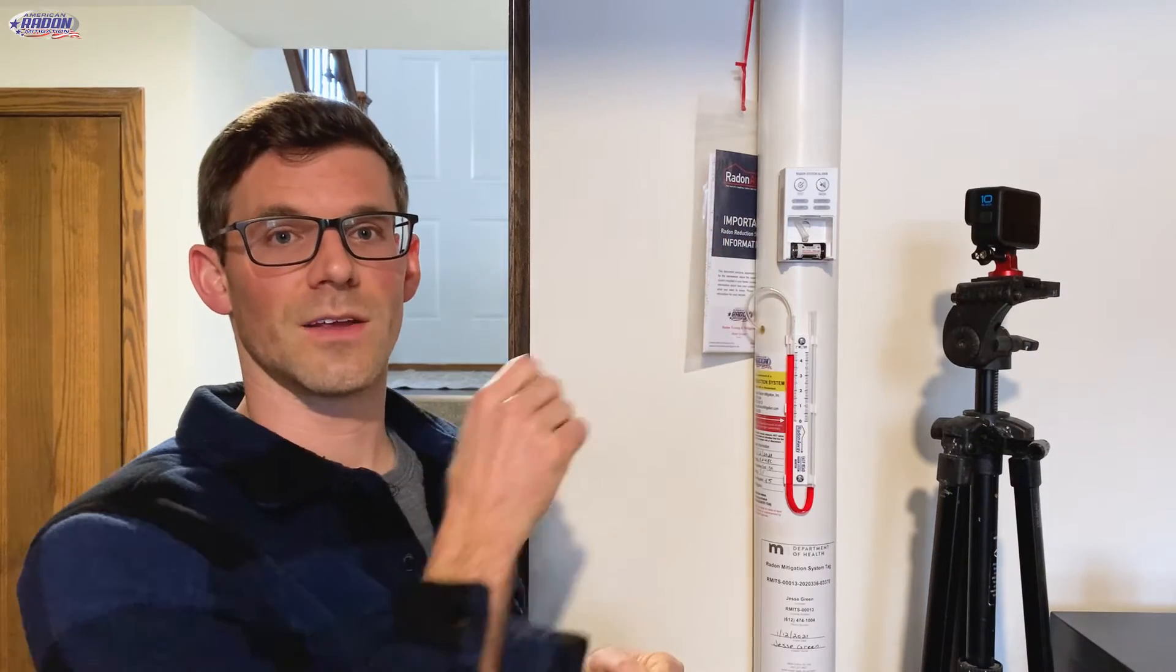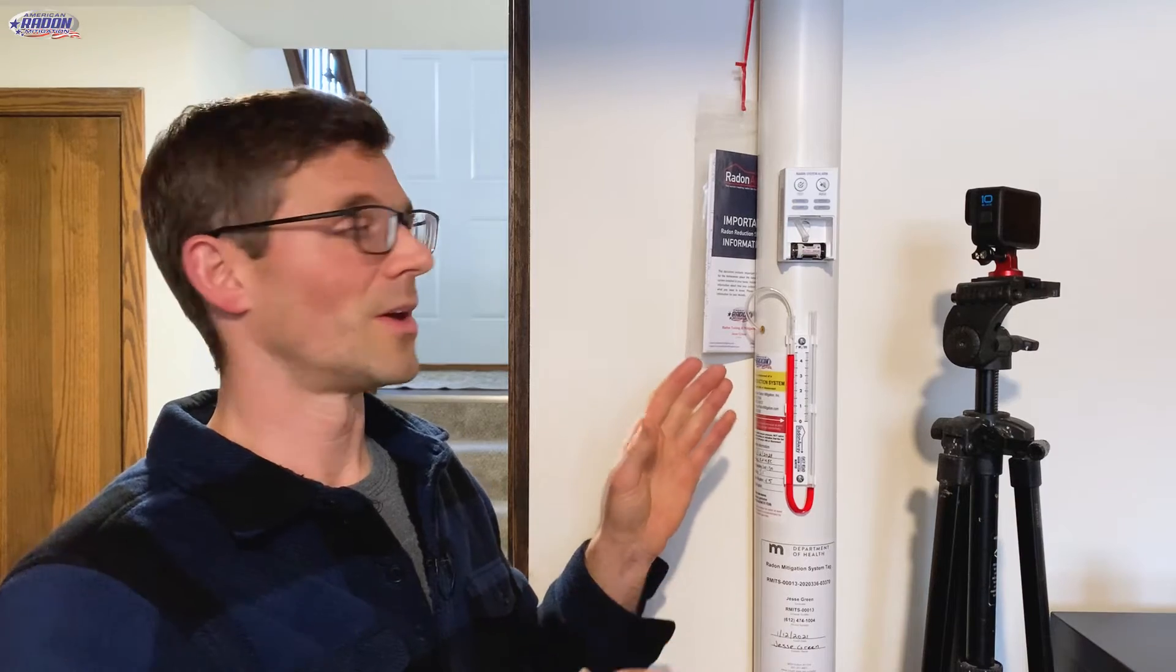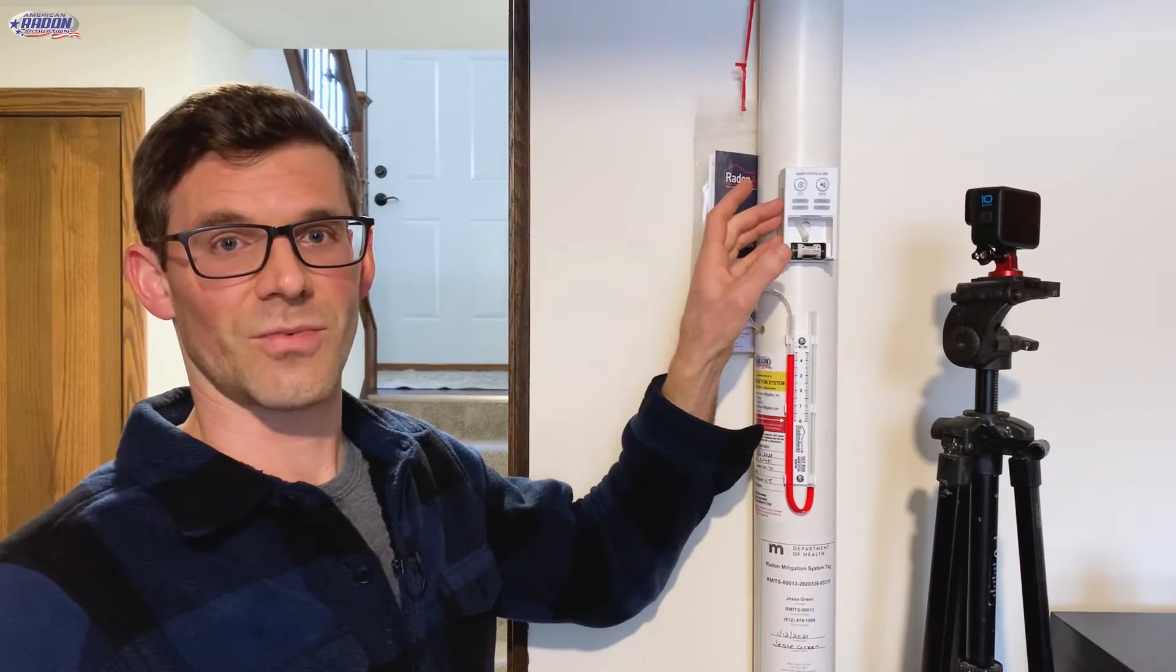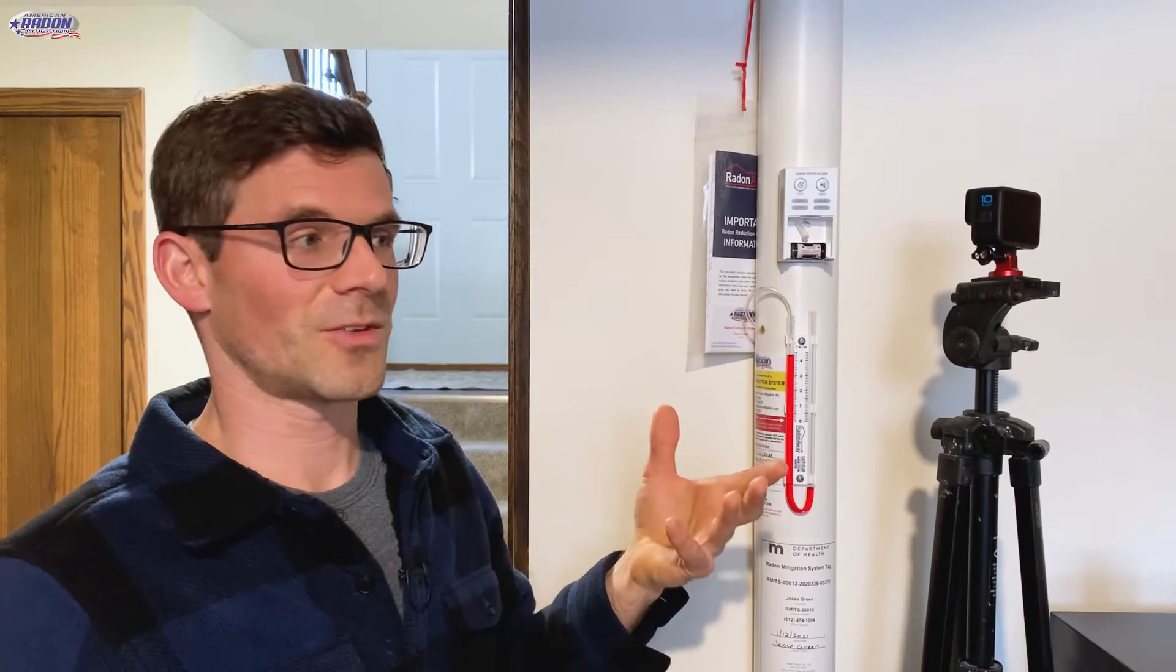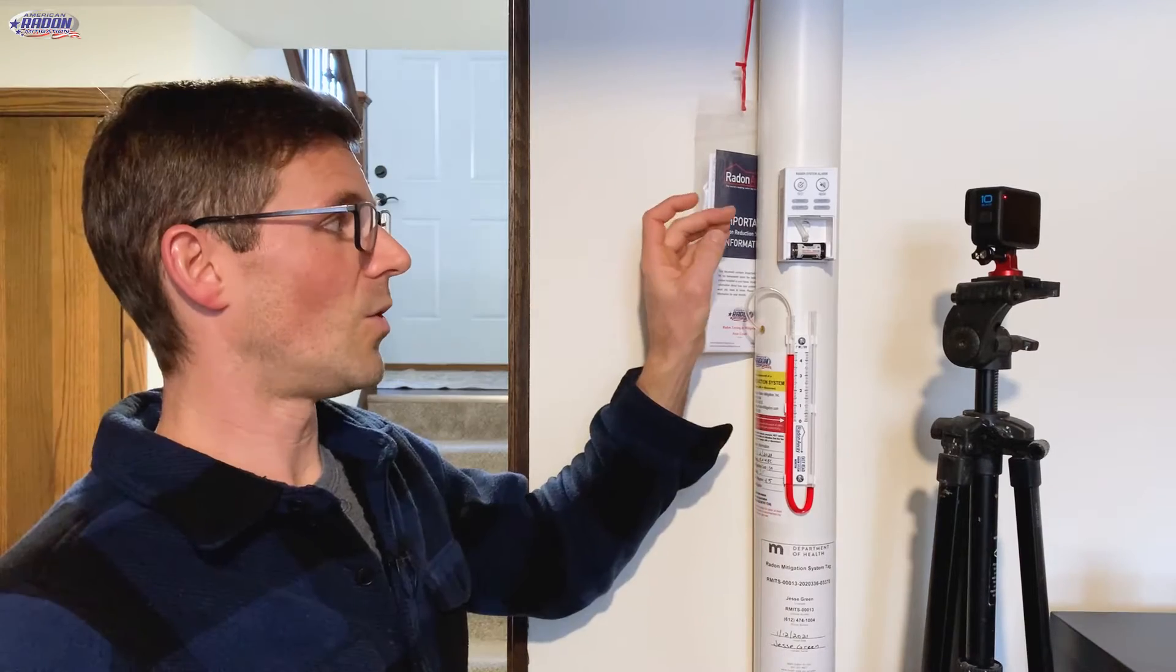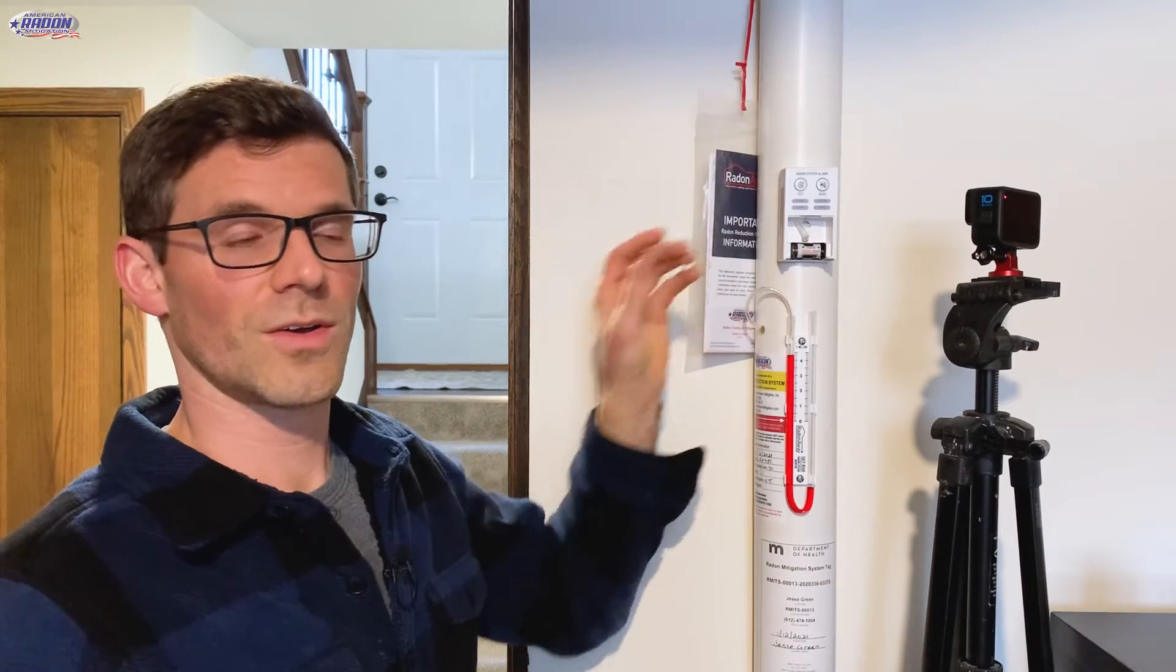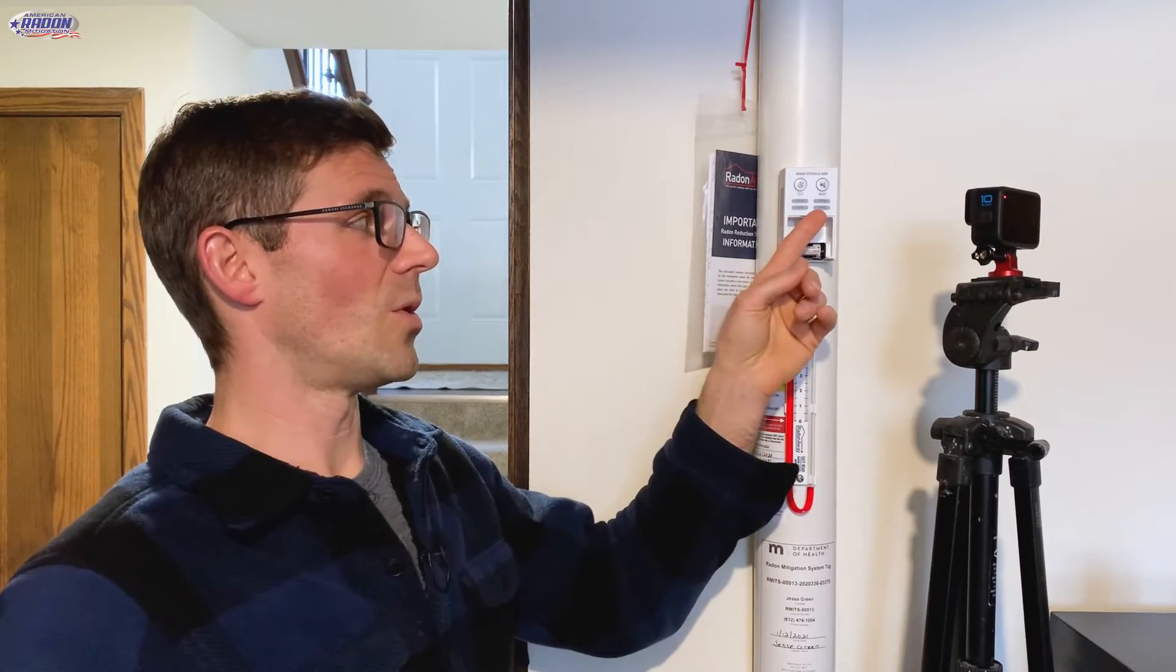So that red light is going to come on every minute. It is not going to continue to chirp. So the customer just didn't hear that first chirp and was probably expecting it to kind of go crazy and chirp, letting him know that the fan was unplugged. So it's going to stay in alarm mode for 48 hours if the pressure isn't restored to it. And then it's going to go into service mode.